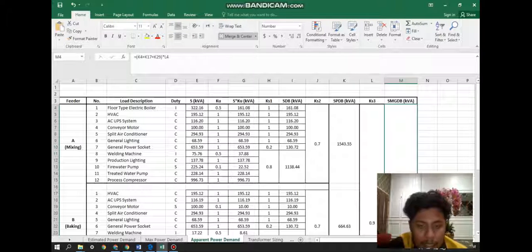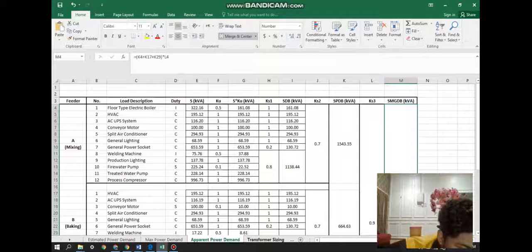So the appropriate rated diversity factor is 0.9, which is found for the total load in KS3 by taking into account the selected rated diversity factors indicated in KS2. So the value of the sub main general distribution board, SMGDB, will be 3281.35 kVA, if KS3 is multiplied by the total of the values mentioned in the SPDB. Okay, so proceed with this.